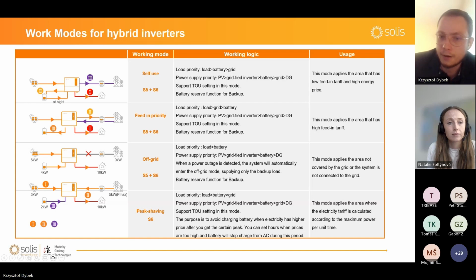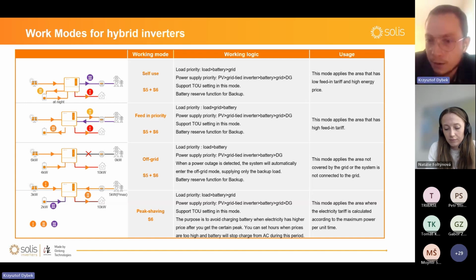Feed-in priority. A very rare situation, I guess, when you have a good deal with your grid operator and they want to use your exported energy to the grid for a reward. The battery will discharge even if your load is covered. So you can set discharge hours in the time of use chart. One thing needs to be mentioned, it comes from simple logic. Self-use cannot be enabled at the same time as feed-in priority. You need to choose one of them. It will actually switch automatically. But only one function can be active. So when you have a grid loss situation on site, or the inverter never had an AC connection with the grid, in this mode your battery will be drained as much as possible because in this kind of scenario every energy source counts.